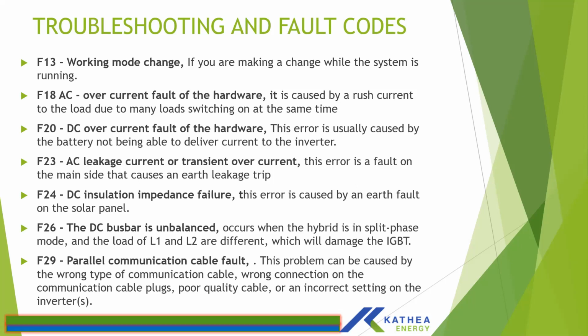So F13 is a working mode change. If you change the system working mode when it's running, when it's powered on, when it was supplying loads and all that, when it was active, and then you change it to parallel mode, then it will give an F13 alarm. So usually for this alarm, you need to just switch off the inverter and power it up again, but preferably all settings are done when the inverter is inactive, that is on but not supplying any loads.